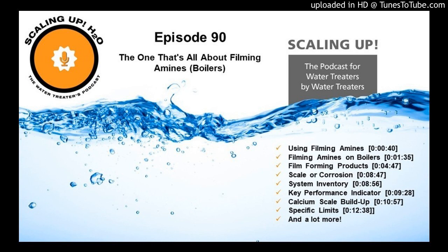The other piece of that is that testing for residual of filming amine is truly no different than testing for residual, like I said, of a different product. I mean, you're ultimately doing the same thing. But rather than me telling you I need you to test 4 different products because you're putting 4 different products in there, I'm telling you you're putting this one item in there, and I want you to test for this item.